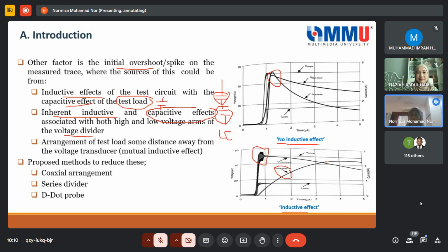The current response exhibits a slower current rise time compared to when you do not have the inductive effect. Okay, so when we analyze this, of course, we may think that it's due to the test load, whereas it's actually due to the inductive component in your test arrangement. Okay, proposed method to reduce this.